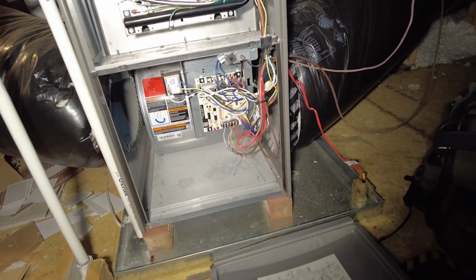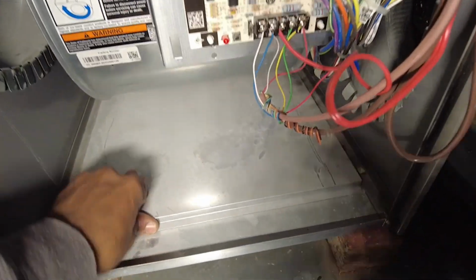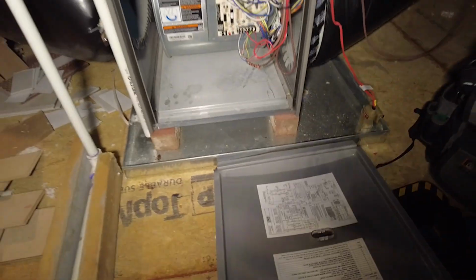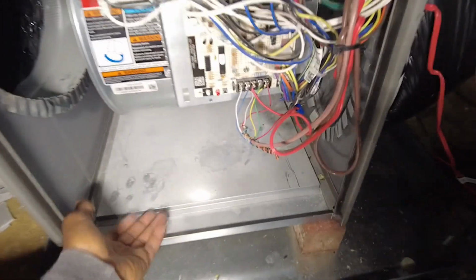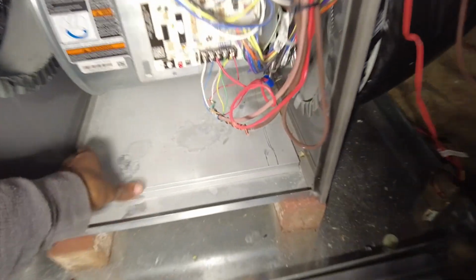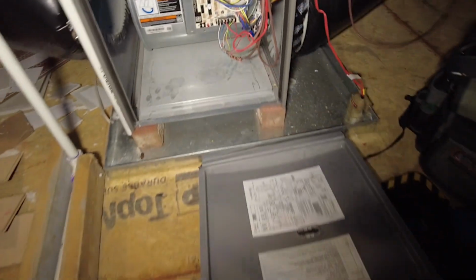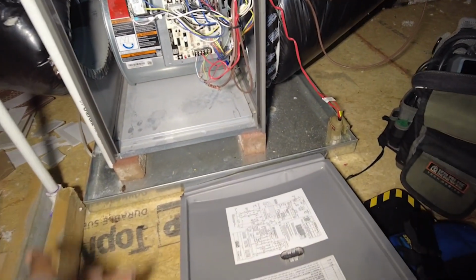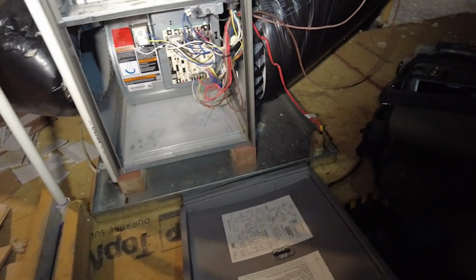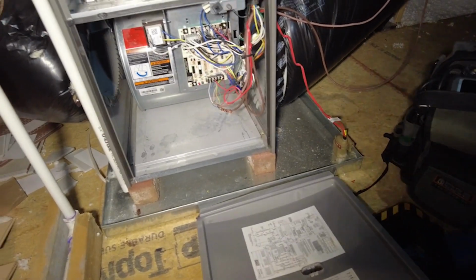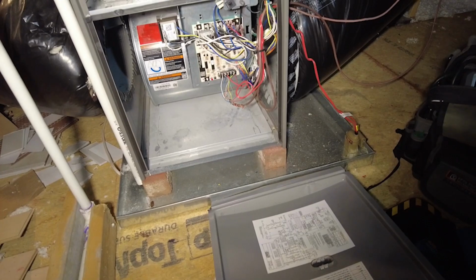So that's it. Make sure the pan and everything is on there solid, not letting the attic air come up in through here. Because imagine sometimes this pan could be loose or disconnected, and all summer it'll be pulling 150-degree attic air up into the return. So these are all things we need to always be looking out for.